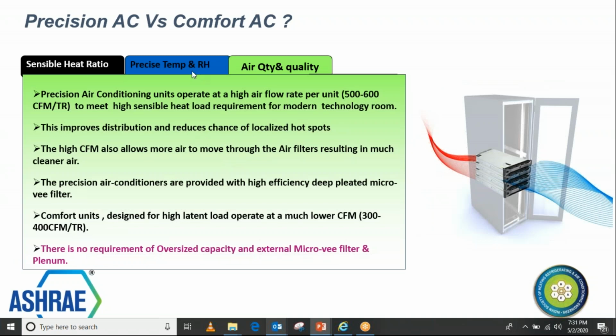Moving forward, another important point is air quality and quantity. We were talking about quality and touched a little on why the filtration level is important in the previous slide. But the CFM is also important in cooling electronics or machines. You need to remove the heat faster. Imagine you have a 1,000 square feet area and a couple of people sitting there. The load density is not really high. The human body dissipates heat, but it is much lower compared to a rack of, let's say, even 4 kilowatt or 5 kilowatt in a 600 to 1200 frame size. So imagine the density of 5 kilowatt versus a few watts.